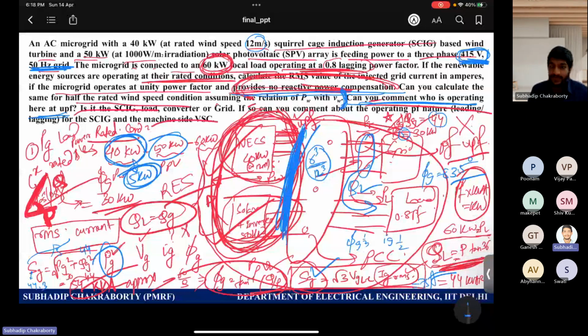This is not a normal condition because we use the inverters to compensate for the load reactive demand to improve the grid power factor. But this problem is framed in such a way to show you that if we don't provide reactive power compensation using the converters of the renewable energy sources, then as your active power injection to the grid reduces, power factor becomes very poor, which can be improved using reactive power compensation by taking advantage of the inverters of the renewable energy sources. So you see that due to the high variability of this renewable energy source, your grid power factor could have been quite varying, right? For which you have been penalized. But due to improved control of the converters tied to the renewable energy sources, we achieve additional advantages out of them by using the inverters, so that the grid power factor is not decreased even during power variation of the renewable energy sources, since the reactive power of the load is provided by the converter.